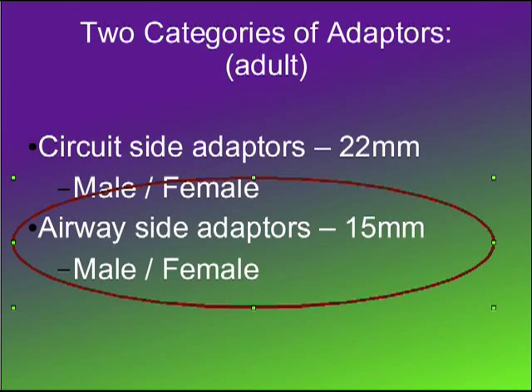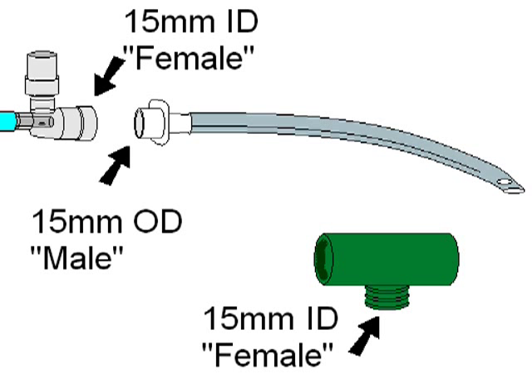Now, what about the other category — the airway side adapters, the 15 millimeter? A good example might be the Ballard inline suction catheter elbow, which can connect to an endotracheal or tracheostomy tube. The end of the trach tube itself has an adapter that's a 15 millimeter OD male because it fits into a 15 millimeter ID female. Also, the center port on the Briggs T adapter has a 15 millimeter ID.